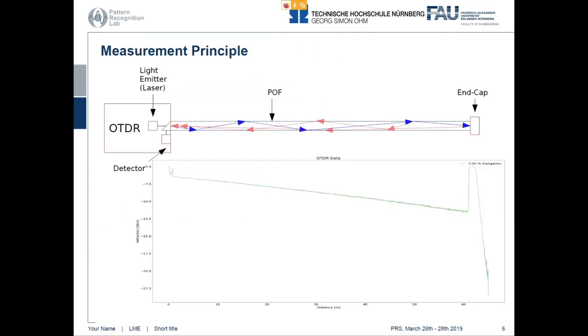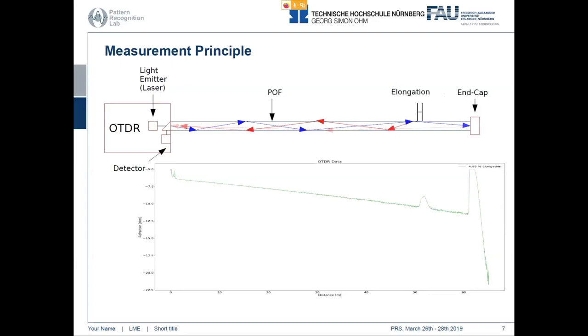So you get a nice measurement curve that starts and then has a constant backscatter until the end cap, where most of the light is reflected, as you can see in this nice steep peak. One nice property of those fibers is if you stretch it at any point, this locally increases the amount of light that is reflected. The effect is the Rayleigh backscatter, and this can be measured by this device. We use this to detect possible movements as early warnings.